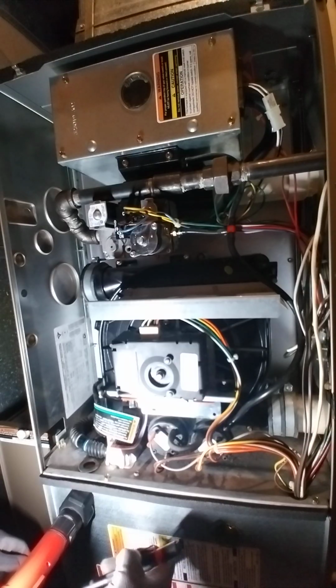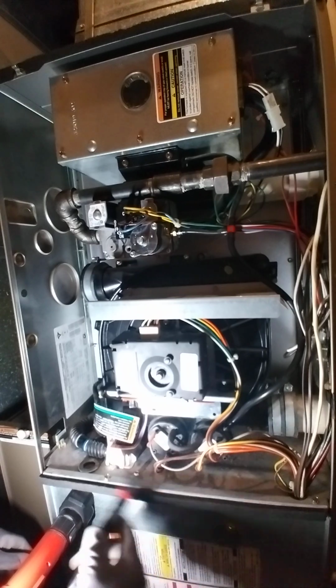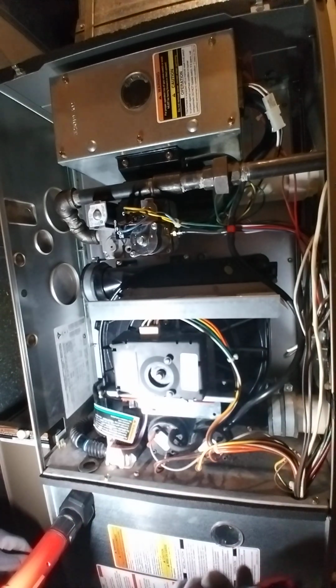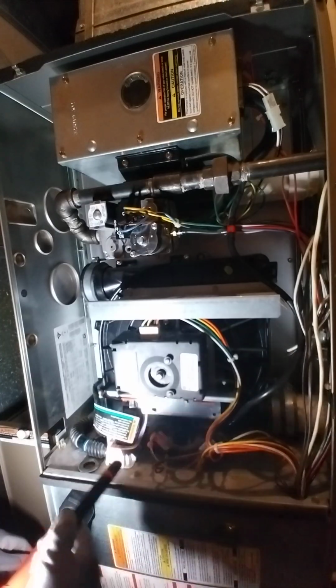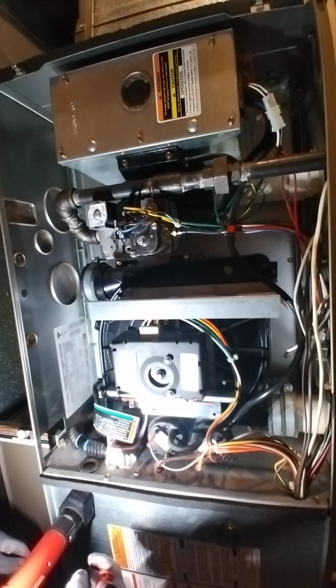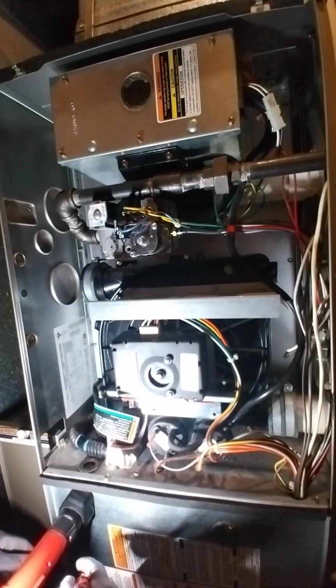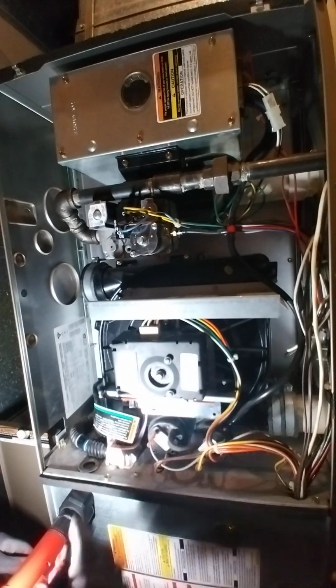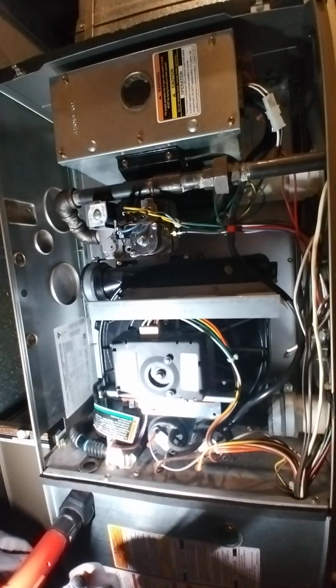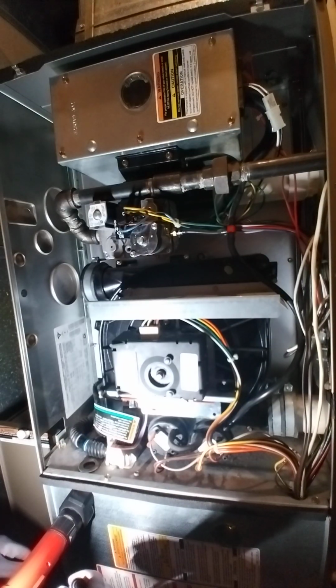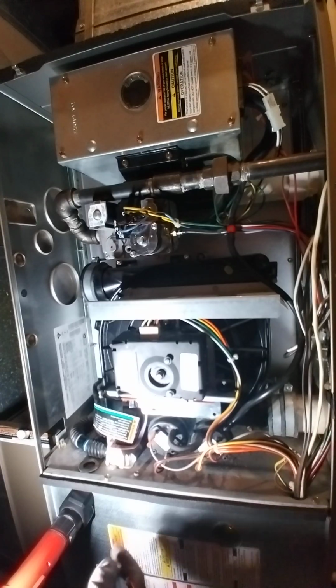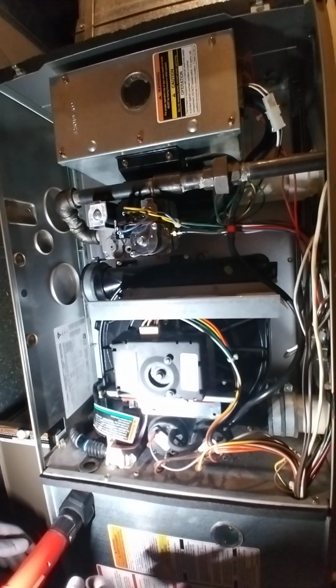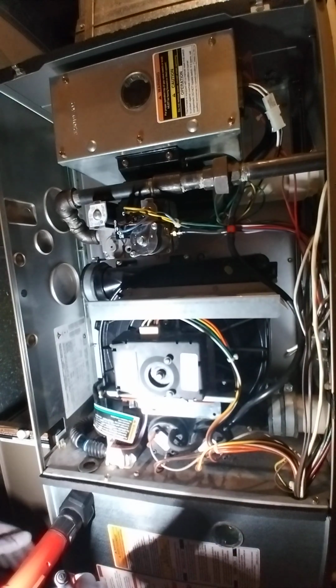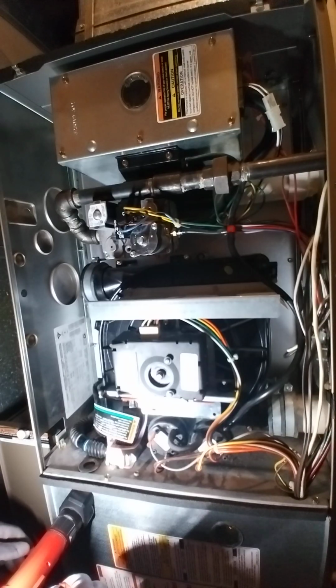So I ended up pouring about 1.5 cups of vinegar, just as a cleaning agent as well, into the system. And I would say out of that drain tube, I got about half a cup that actually came out, which means that this thing ended up holding roughly a cup of that vinegar. And as soon as I did that, the furnace ran without an issue. The sensor wasn't dropping out, the furnace wasn't short cycling, and no problems, it ran like it did before. So that for me really confirmed that the maintenance tech is who caused this issue to begin with. And again, I've since fired them, because this is actually the second time that we've had some inconsistent and not high quality work from them.